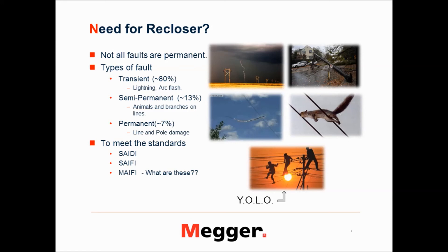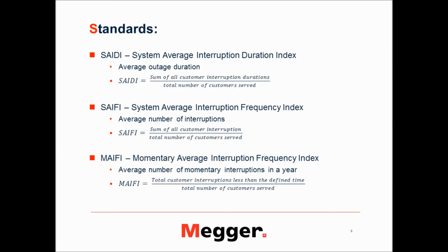Another important need for reclosers is to maintain standards like SAIDI and MAIFI. SAIDI stands for System Average Interruption Duration Index, and it tells you the average outage duration. It is a ratio of the sum of all customer interruption durations divided by the number of customers served. You want to keep this index within the threshold, because a higher index means more interruptions in your system, and generally customer satisfaction is very low when you have lots of interruptions.